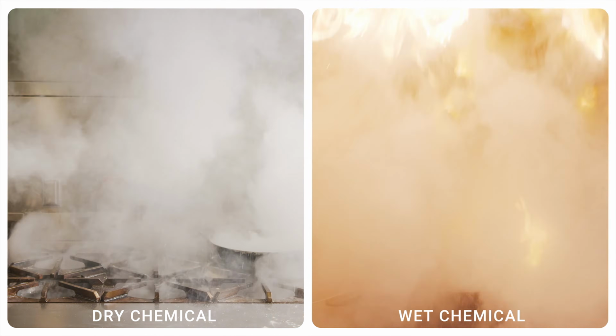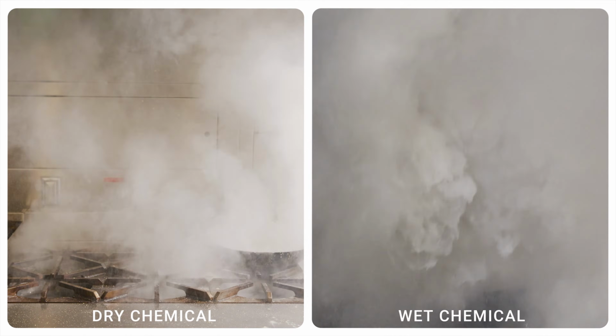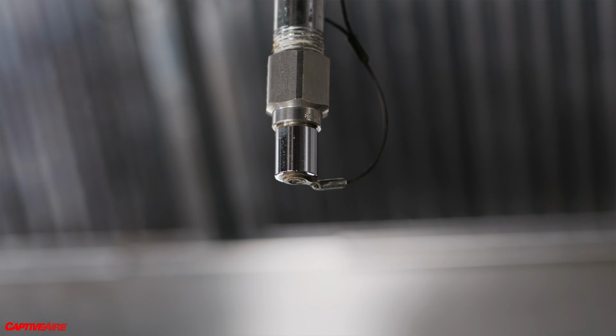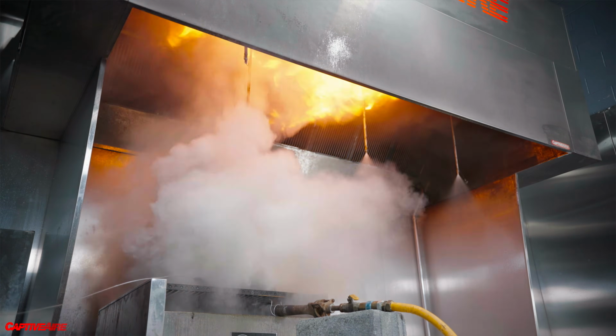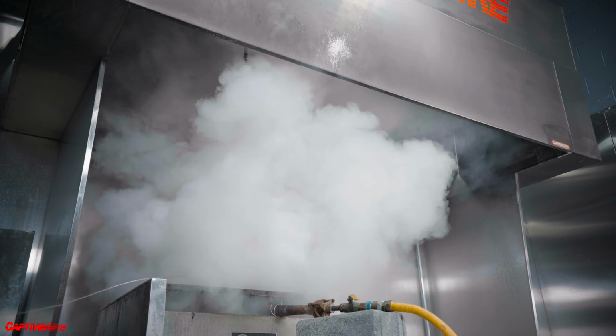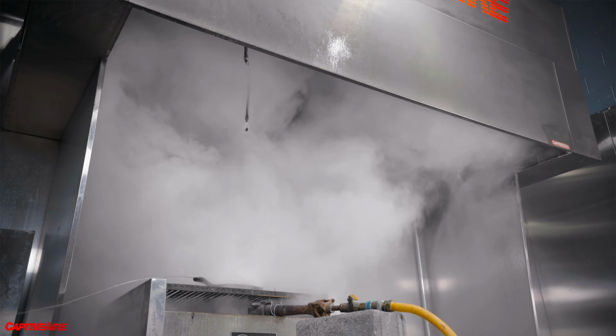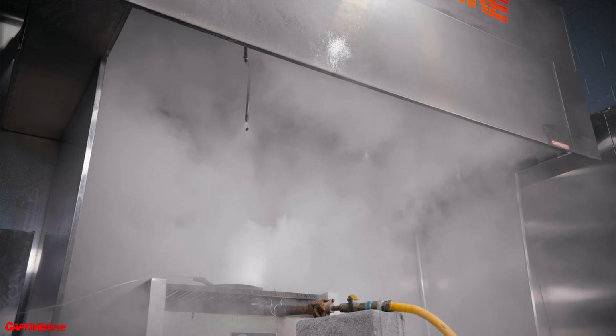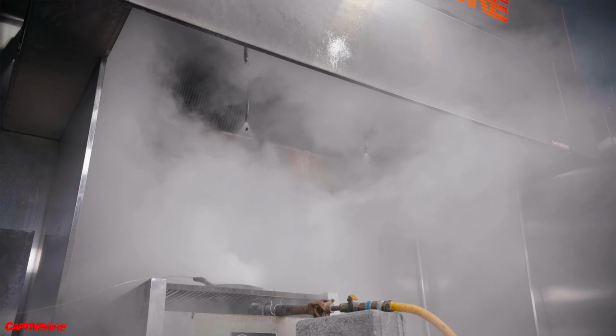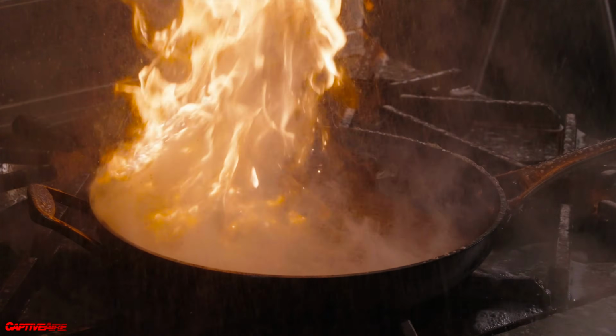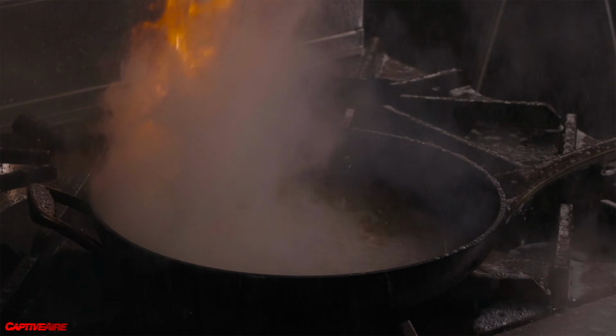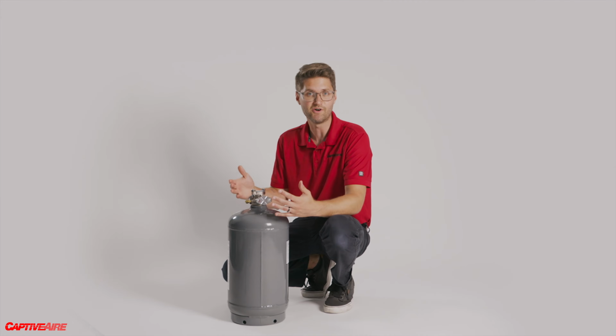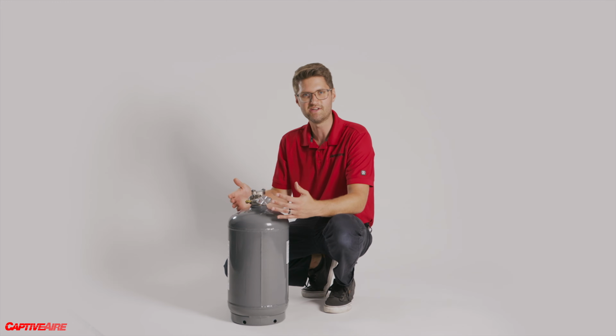With wet chemicals, you add water into the equation, and the nice thing about water is you can actually take heat out of the appliances. As we use more vegetable oil, the cooking process gets much hotter, so we need to suppress the fire and remove heat from the appliances. That's what wet chemicals do - they effectively remove heat. Wet chemical systems do work, and they work really well under controlled conditions.